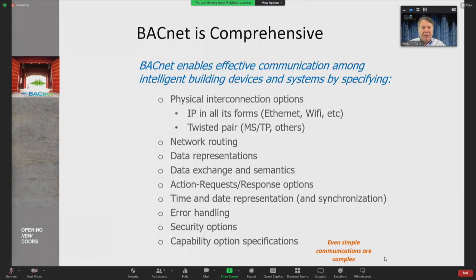And then there are a set of rules about how you define what capabilities the device has - what is the device profile, what has to be included to qualify for a profile, things like that. So all of that is part of BACnet. It defines the messages and formats, how messages are carried and routed from one place to another, and what they look like on the wire. You need all of that, or you can't have devices independently developed that will actually just work together.